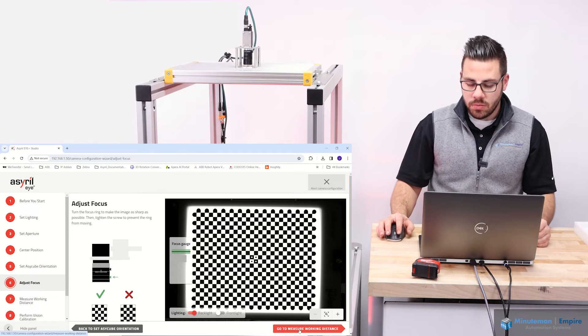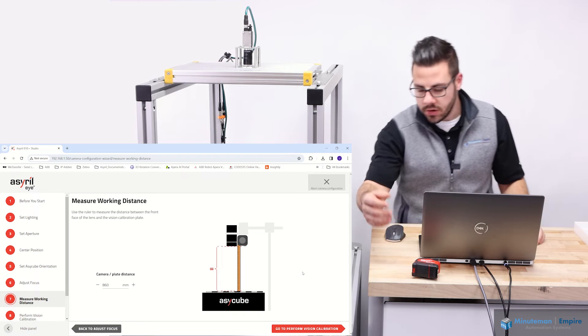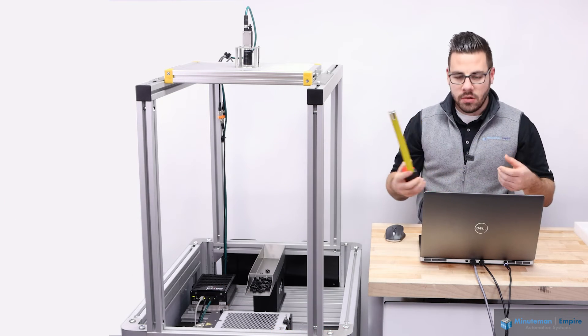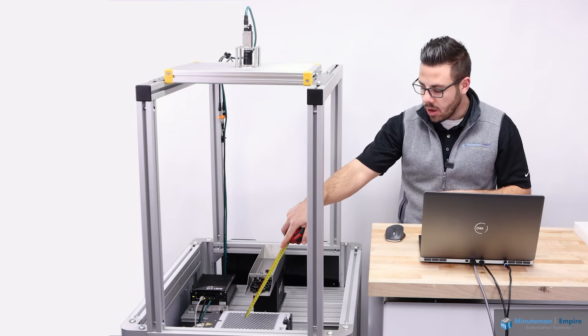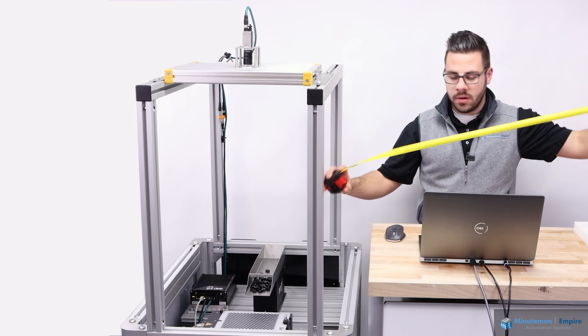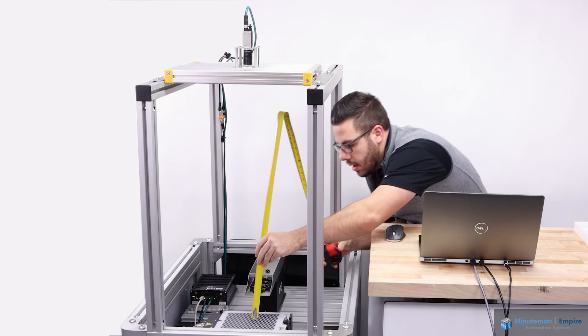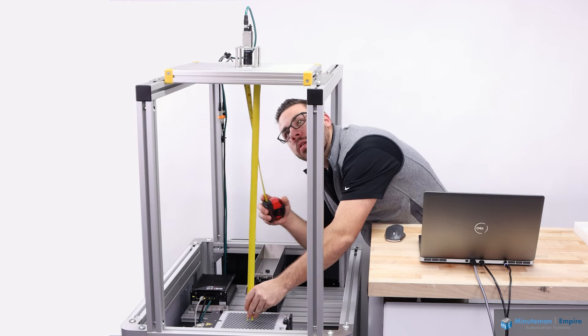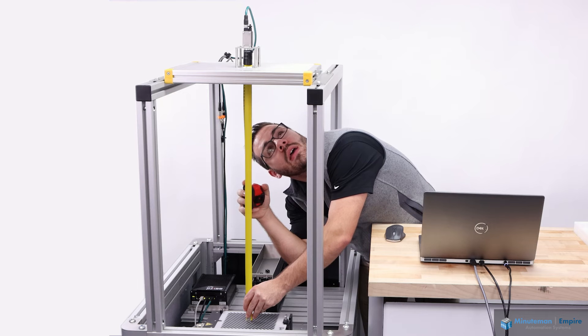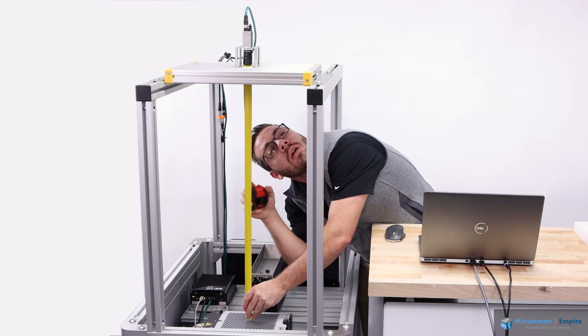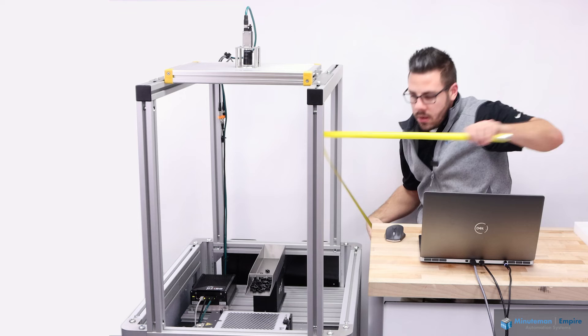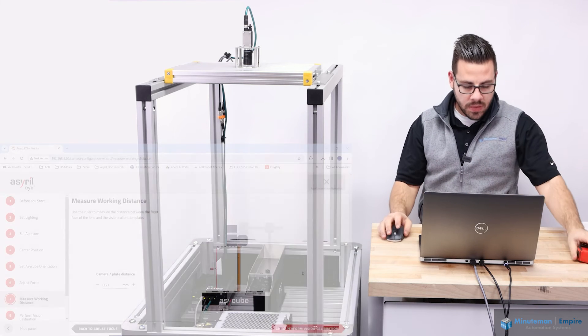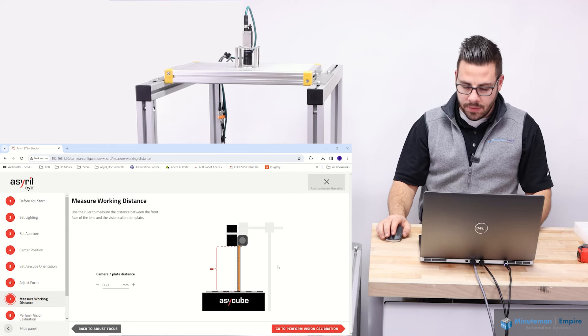Next, I'm going to go to measure working distance. Here's where my measuring device comes into play. I'm going to measure from the calibration plate to the front part of the lens. We had 860 before. I'm just going to go in and measure. We're looking at about 860 again. So it's critical that you put that dimension in there. We're going to leave it at 860.